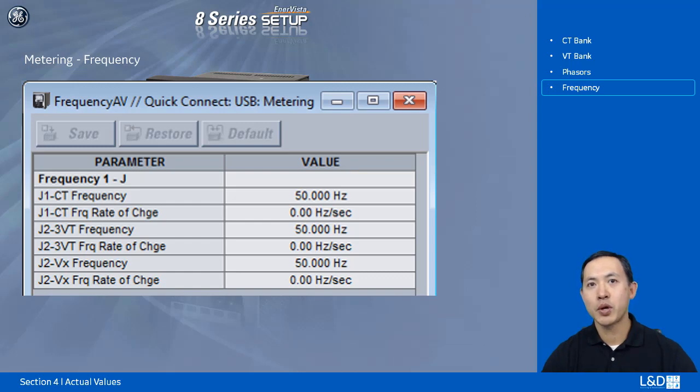The main frequency tracking source uses three-phase bus voltage. The frequency tracking is switched automatically by algorithm to the alternative reference source, then three-phase current signal or line voltage, if the frequency detected from the three-phase voltage input is declared invalid.